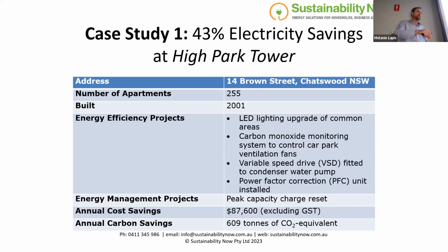So we put pressure transducers on the pipework and control valves on the actual air conditioning units. When no one's using a unit, a little motorized valve shuts off the water to it. Pressure builds up in the pipework, the pressure transducer reads that and goes, hey, we don't need to run so fast, and tells the VSD to slow the pump down. These sort of things give massive savings. We did that there. We did a power factor correction unit. We reset their peak demand, and they saved 87 grand a year, 87.5 grand a year.